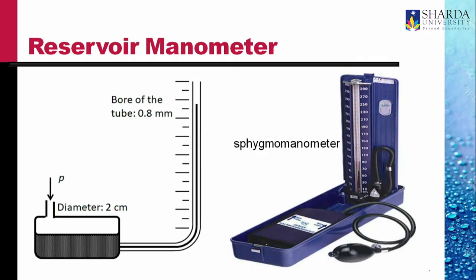This is used in a conventional blood pressure measuring equipment. At the bottom there is a relatively large reservoir of mercury connected to a very fine bore tube against a scale. It is kept vertical, and when pressure is applied to the reservoir, mercury rises as a column within the capillary. By reading the height of the mercury column on the fixed scale provided, we can calculate the pressure head.